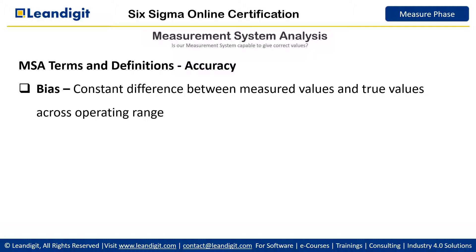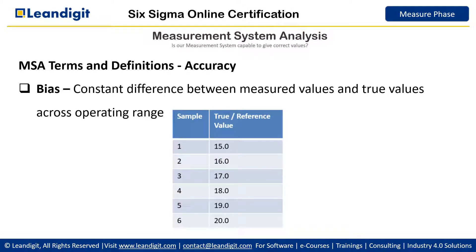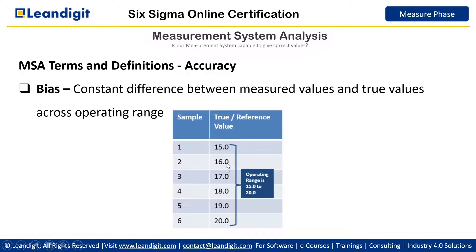Bias is a constant difference between measured values and the true value across the operating range. For example, we have taken six samples across the entire operating range, where the value of the first sample is exactly 15 and the value of sample 2 is exactly 16. These values are measured using a master instrument. 15 to 20 is the operating range of the process.